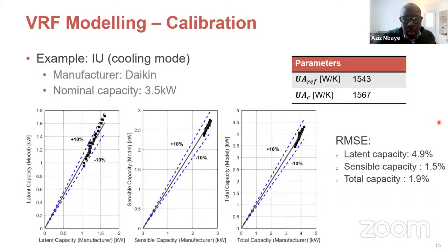And here is an example of the calibration procedure tested on an indoor unit of a nominal capacity of 3.5 kilowatt from the manufacturer Daikin. Here we represented the result for the latent capacities. On the x-axis, we have the manufacturer value, and on the y-axis, we have the value of the model.